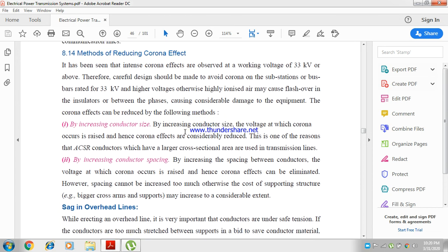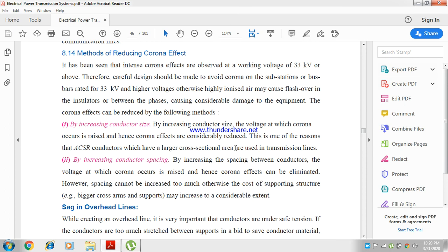By increasing the conductor size. By increasing the conductor size, the voltage at which corona occurs is raised and hence the corona effects are considerably reduced. This is one of the reasons that ACSR conductors, which have a larger cross-sectional area, are used in transmission lines.